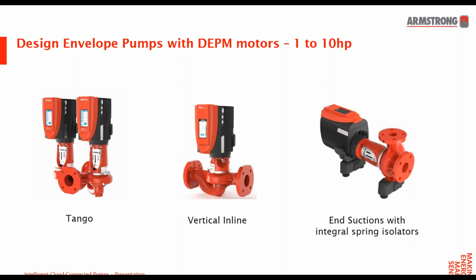If it was a base mounted pump, like even the one on the right there, the end suctions with the integral spring isolators, for those ones, we do recommend having flex connectors, because now they're mounted to the ground and you don't want to have any vibration or water hammer or anything transferred to the rest of the building.